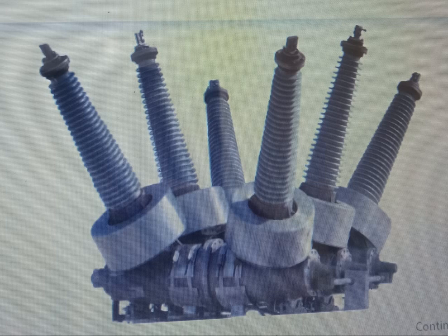This leads to a rise in temperature, and the heat produced is sufficient to ionize the medium, whether air or oil. The ionized medium acts as a conductor and an arc is struck. This ionized medium provides a low resistance path for the current to pass. So we have to extinguish the arc.